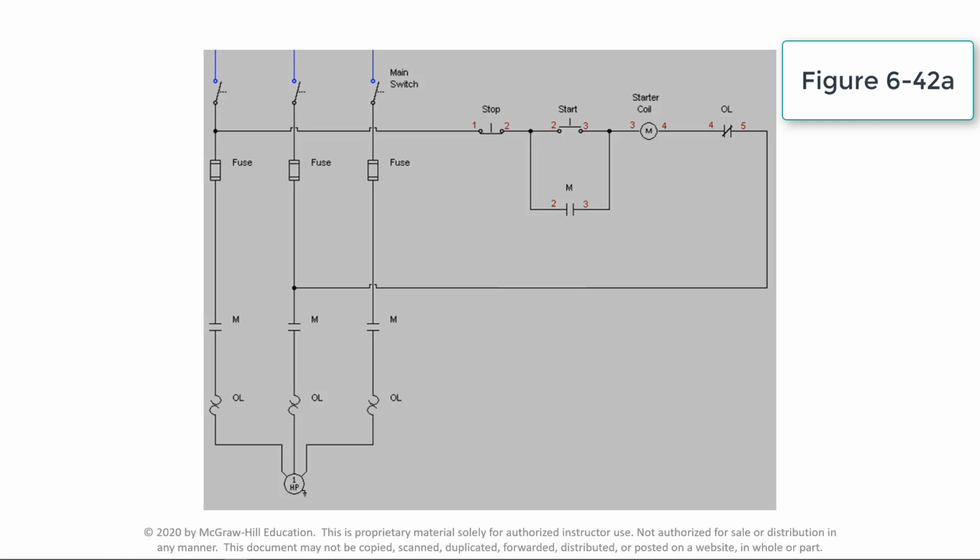This video demonstrates the operation of a thermal overload relay circuit with manual reset only. A thermal overload relay uses a heater element connected in series with the motor supply. Current flowing from the motor contactor to the motor passes through the motor overload heaters, one per phase, which are mounted in the overload relay block.